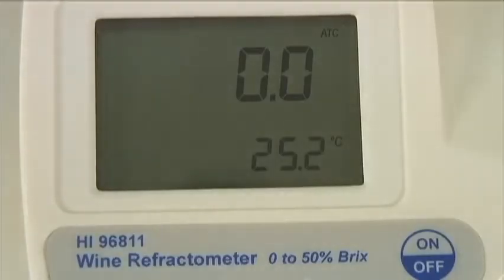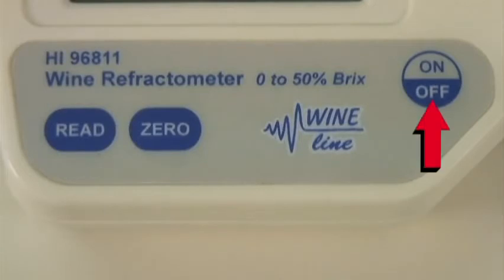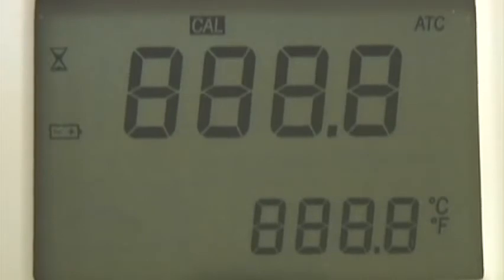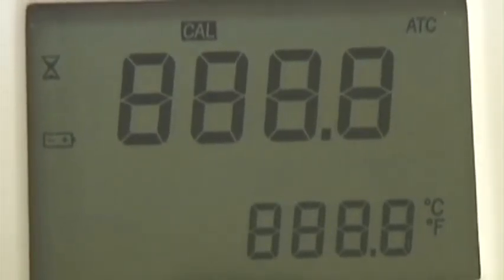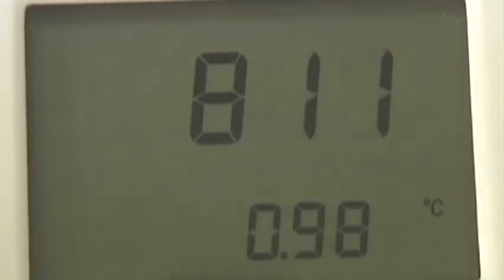As you can see, the temperature is displayed here. The units can be changed between Celsius and Fahrenheit. Simply press and hold the on-off button for about 8 seconds. If the refractometer turns off, that's alright. Simply press and hold on-off again for 8 seconds. During this time, the LCD will display all of the segments. And don't worry, the refractometer hasn't lost your calibration. When the model number shows up, keep holding on-off and press the 0 key to change the temperature units.